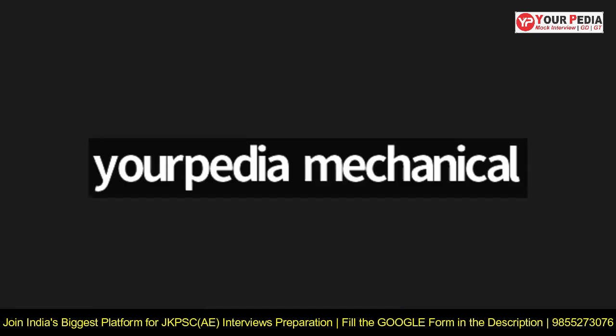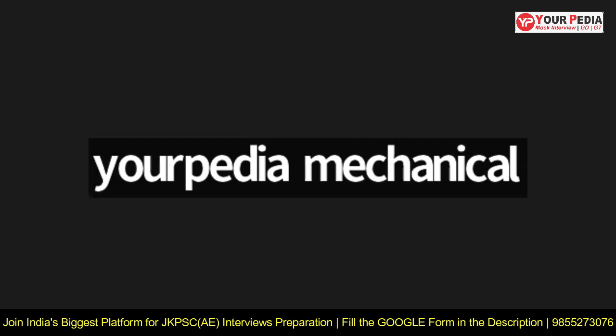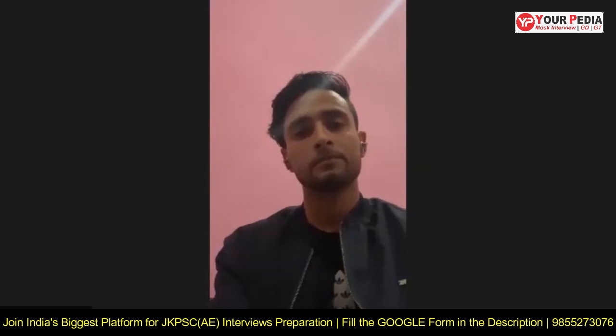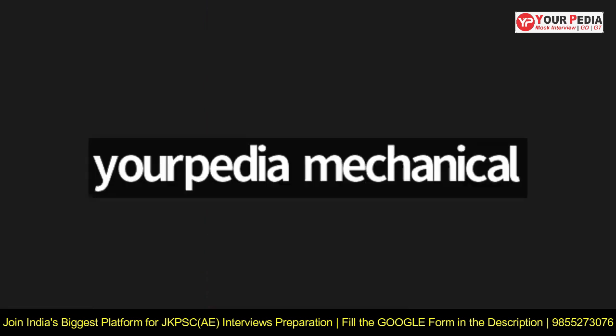So some very simple questions you missed, although some questions you answered correctly, but very clearly you need to highlight. Like I asked why we cannot use isentropic expansion in VCRS. What do you need to say? For carrying out the isentropic expansion, we need to attach some kind of expansion device, a piston cylinder arrangement or turbine. At the end of the condenser we are having liquid in VCRS, and liquids are incompressible. So even if a liquid is at a high pressure, if you carry out its expansion, we are not going to get any significant work out of that.